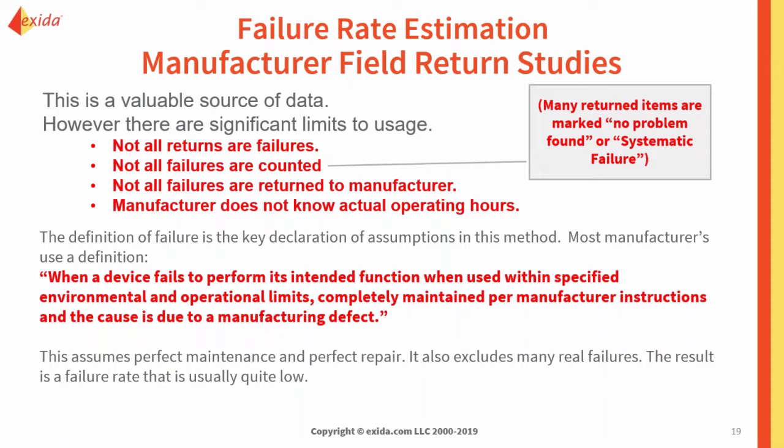So first of all, if you're thinking about doing a manufacturer field return study, think about what the product is. Are all returns going to be told to you or not? Are all failures counted? A lot of companies mark, oh, no problem found, or systematic failure, end user, and don't actually look into why it broke or what happened. A lot of the times it's just a check box to mark off and move on to the next part. Once again, not all failures are returned to the manufacturer, and the manufacturer might not know the actual operating hours. Sometimes there's a counter on them, but oftentimes you don't know if a person is going to buy multiple and they're just going to sit on the shelf in case something breaks.